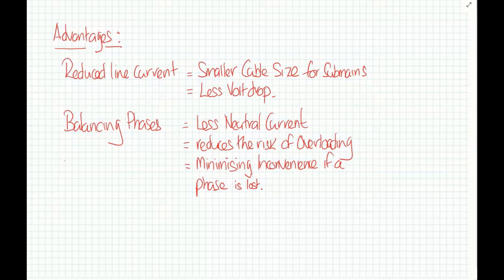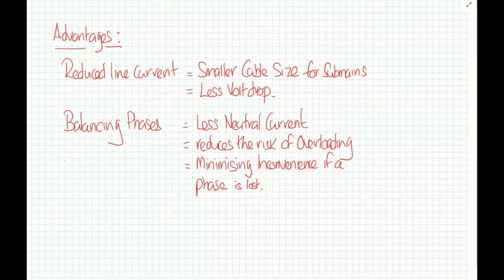The bottom line is keep your loads as balanced the best you can. Don't forget to test your neutrals during your continuity testing. In the guidance notes three, the neutrals often get neglected on new installations. I think it's important that we test the continuity of the neutrals to make sure all those connections are nice and tight. Remember that the neutral is a live conductor as well. Hope you've enjoyed this video, please click the like and subscribe button. Thanks again for watching, see you next time.